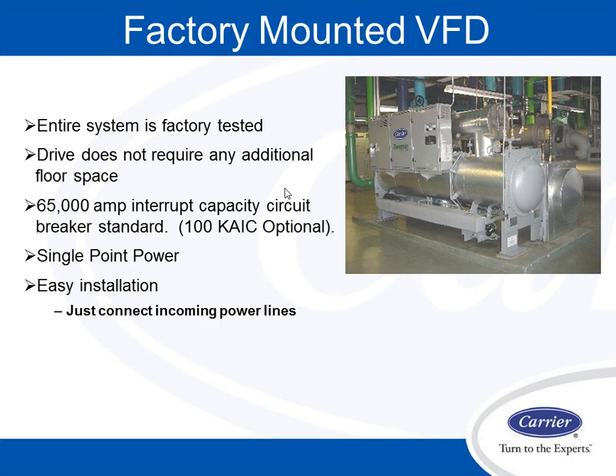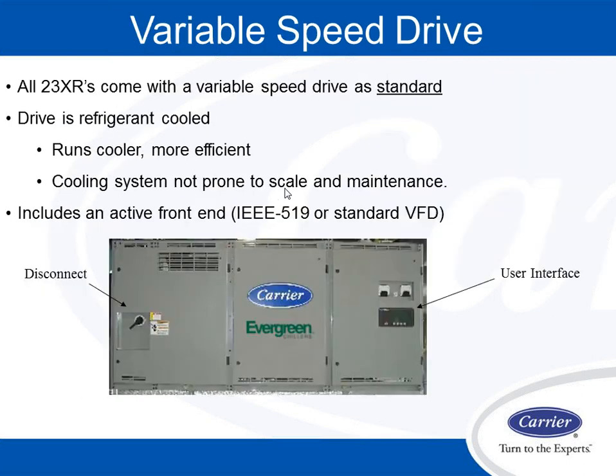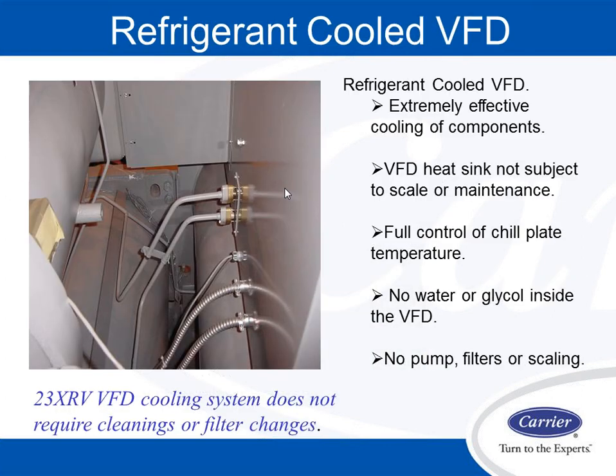Unit-mounted VFD. This is one of the things I'm going to go to briefly here. Standard is a 65K interrupt. Optional is 100K. The one thing is we can get the VFD with an IEEE 519 filter, or we can use a standard VFD on it. Either way, one of the most important things is that the drive is refrigerant cooled. It's not water cooled, it's refrigerant cooled. Okay, that's the factory mounted drive on what we have.